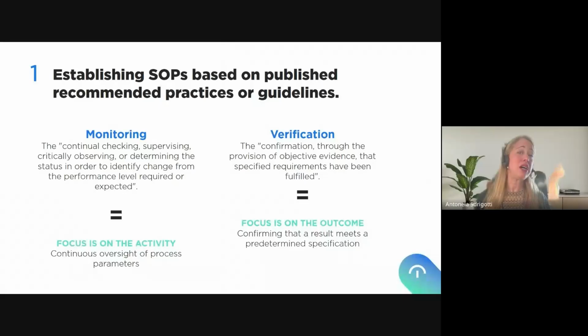And we also have what we call routine control. Okay, this is validation. Normally, and in most countries, it is once per year, at least the performance qualification and the operational qualification. But we also have routine control. And in routine control, we have two different aspects of routine control. We have monitoring and we have verification.